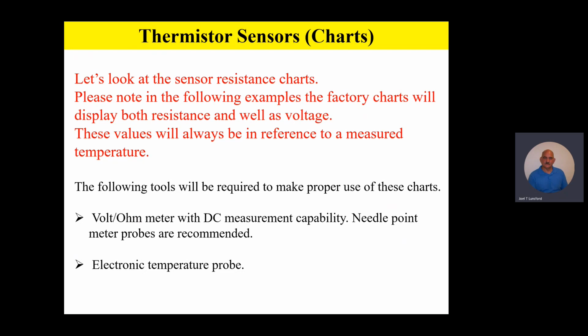So the following tools that we're going to have to properly utilize the sensor charts and to properly check sensors are as follows. We're going to need a good high quality volt ohm meter with DC voltage measurement capability. In addition, I'm going to recommend that you have needlepoint meter probes as well. The reason we want the needlepoint meter leads is once we pull the sensor off and do some checks on it, we can plug it back onto the board, and our sensor charts will actually tell us the DC voltage with the sensor plugged back onto the board. But in order to get into the harness itself, to sneak in behind that sensor plug with it plugged into the board, needlepoint meter leads are extremely handy to read the DC voltage of the sensor with it plugged back onto the board.